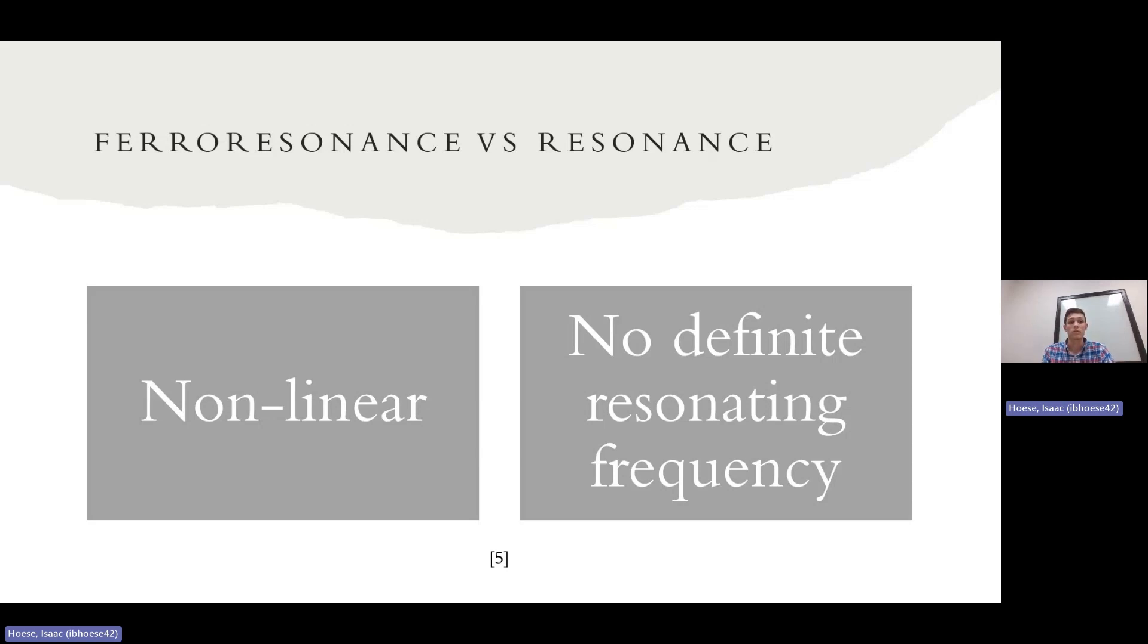The main difference is there's really two. One, it's non-linear. Ferroresonance does have a linear component, but it also has a knee and saturation component, which we'll see in a few minutes. That comes from the BH characteristic curve of the transformer itself.